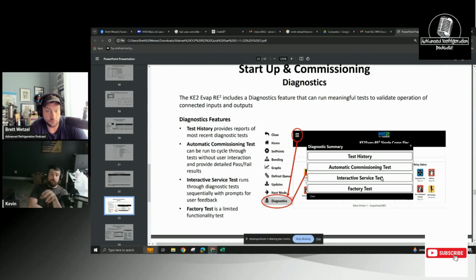I'll say this: none of the liquid line solenoids had been landed when I went to do these. They're all curled up in the bottom of the case for the glycol solenoids. So what I did was jumper power off the lights, because it's 120 volts coming in. I checked this because the KE2s, contrary to everybody else, have Form C contacts, but the common is on the right-hand side of the controller, where everybody else's would be normally closed, on the lighting contact, the fan contact, and the refrigeration contact.